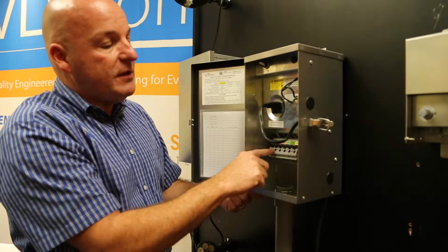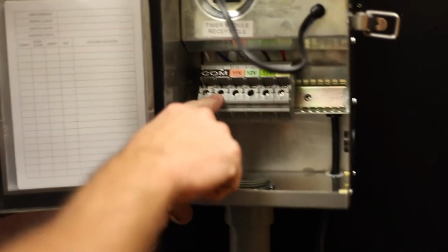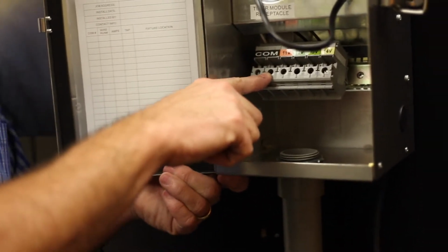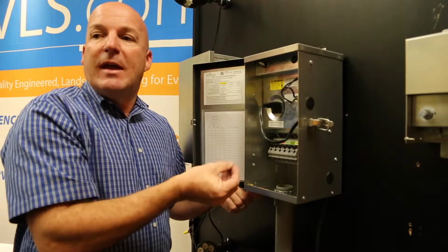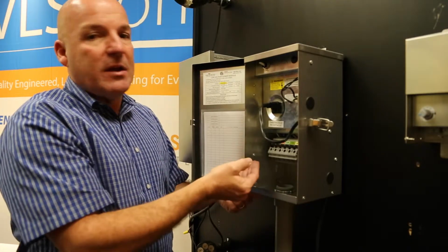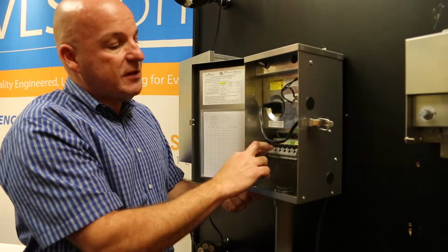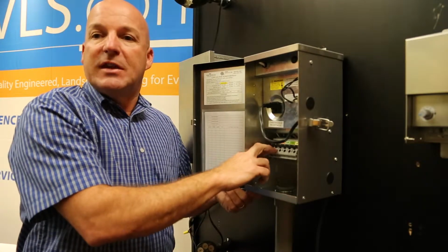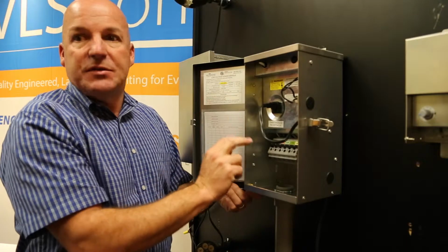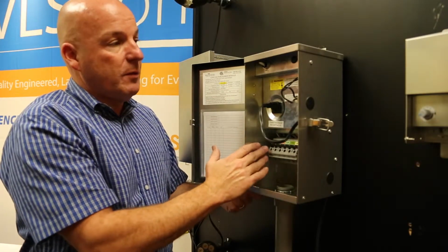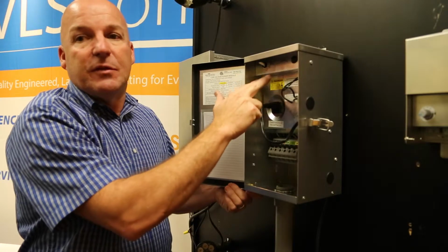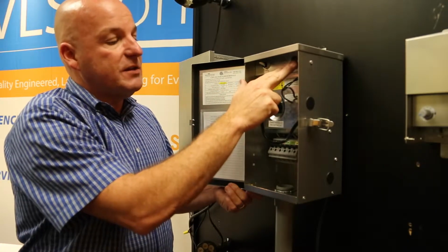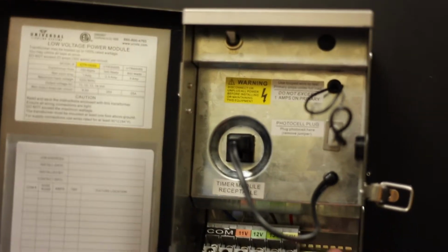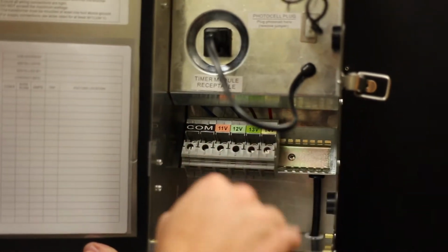We added 2 commons for each circuit. As LEDs become more prominent in landscape lighting, we're seeing many more home runs of wire coming into the system, so we were running out of space on the commons. This happens to be 100 watt, but if we had a 300 watt, we'd still have 2 commons — just more real estate. These 2 commons are associated with a single circuit. If we had a 600 watt transformer, we'd have 2 circuit breakers indicating the different wattages, 300 watts and 300 watts, with 2 commons here and 2 commons here, widely separated so it's easy to identify which is which.